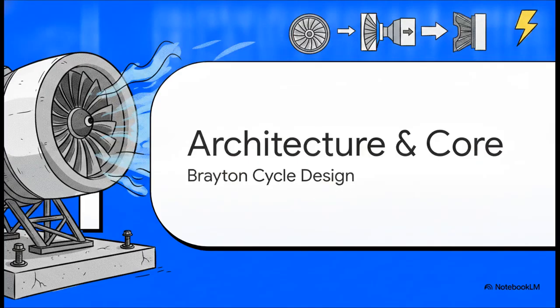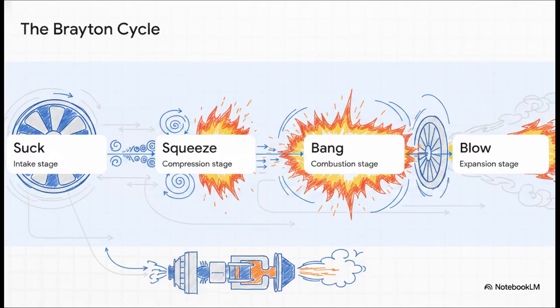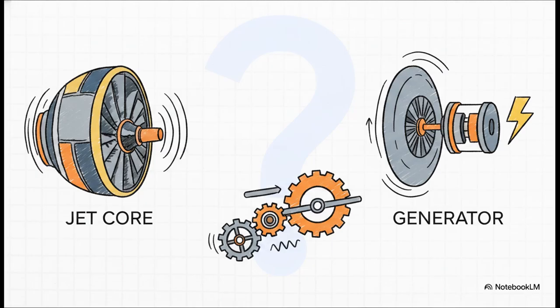Okay, let's jump straight into Section 1, looking at the architecture and core of this two-shaft design. So, mechanically speaking, you're essentially dealing with a commercial jet engine that happens to be bolted securely to a concrete pad. You guys already know the Brayton cycle, but remember, unlike a reciprocating engine, this gas turbine is running all four of those stages, the suck, squeeze, bang, and blow, continuously and all at exactly the same time. Air is constantly being pulled into the front, hot gas blasts out the back, and that gives us this beautifully smooth, highly throttleable power.